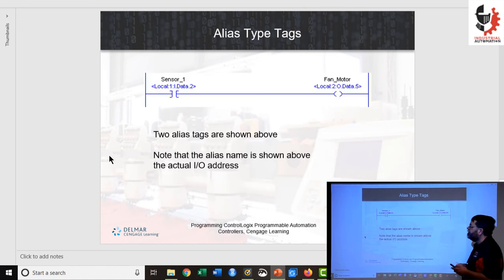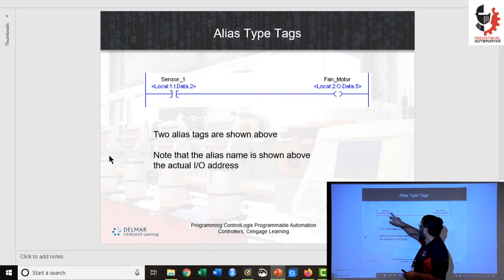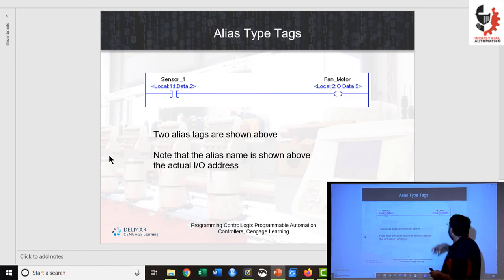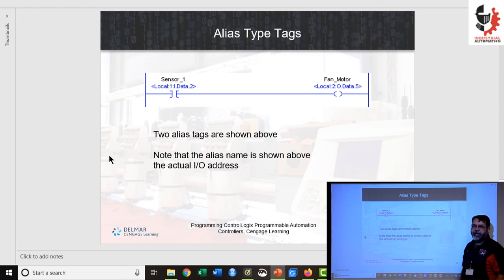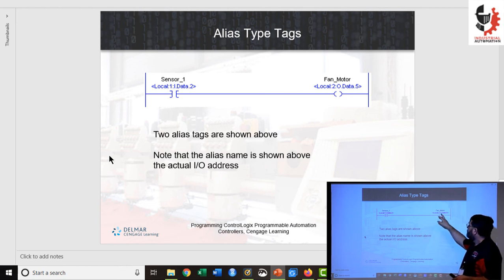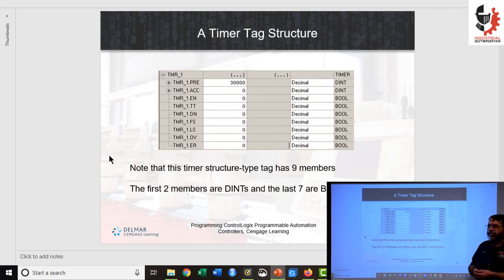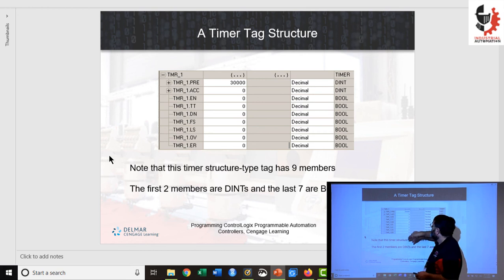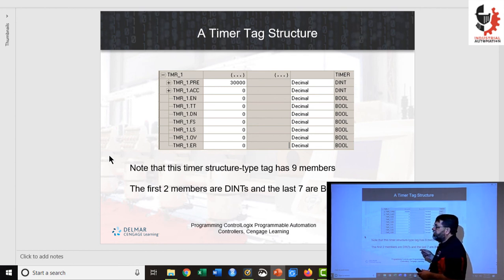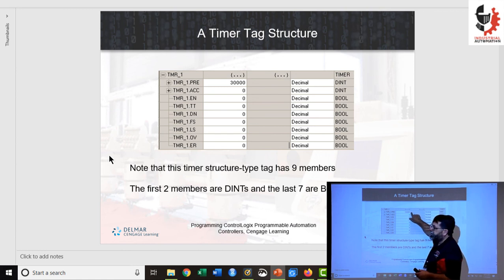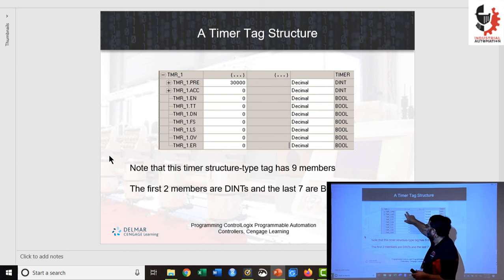Here are a couple of tag examples. Instead of using the hardware address, we use a name like 'sensor1' which tells us where that input comes from. For an output, instead of using 'Local:2:O.Data.5' — which is not very intuitive — we give it an alias tag of 'fan motor' so we know what that output is. We know that when the sensor is hot we're going to send an output to that fan. We also work with timer tags, which have different attributes. The preset (PRE) is the timer duration, and timers are always in milliseconds, so 30,000 equals a 30-second timer.